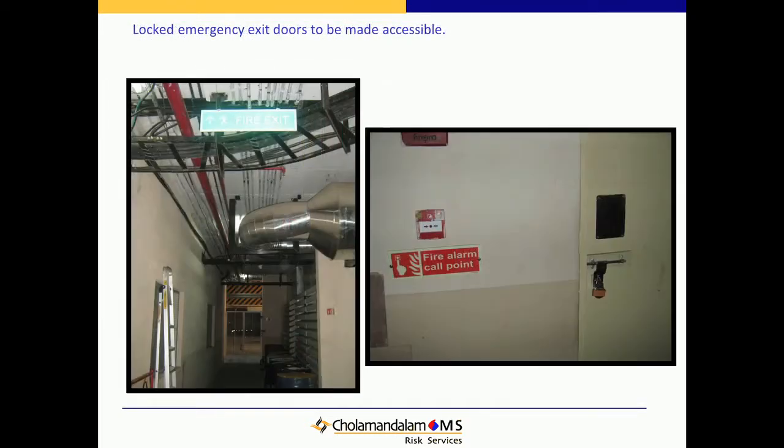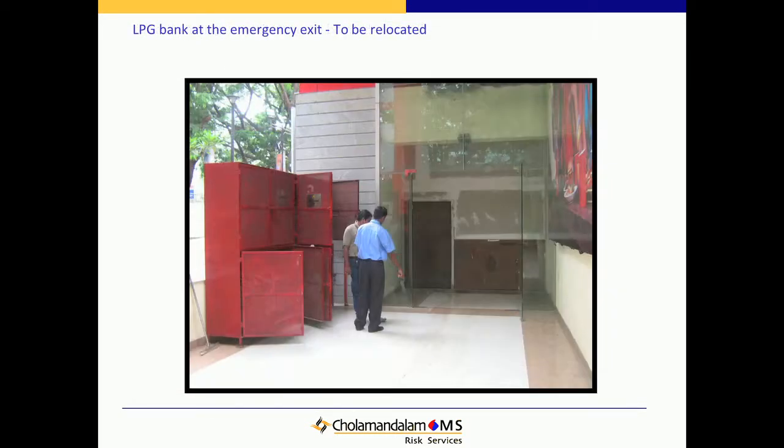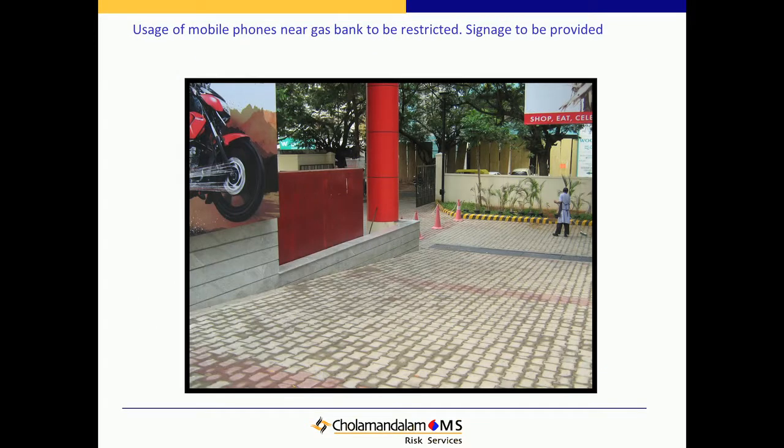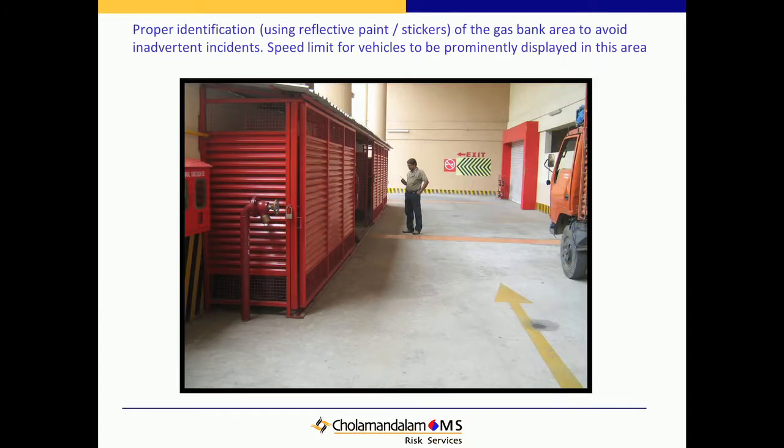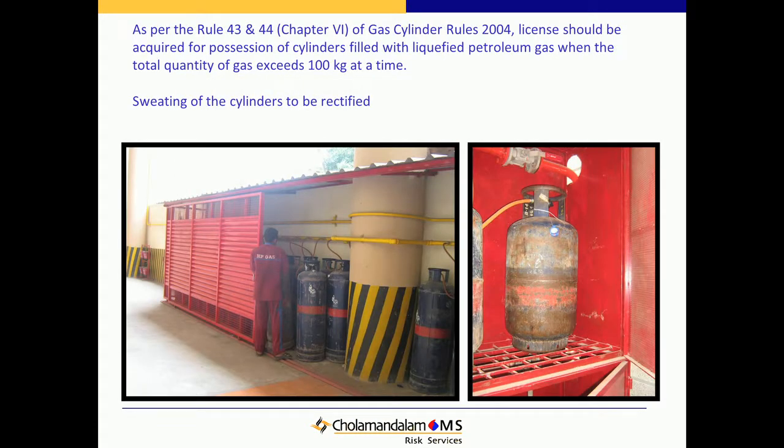See, you have a lot of LPG cylinders that are used for the kitchens there. See how they are located in the area where the vehicles are moving. So there is a possibility of them getting damaged by vehicles hitting them, and they are not properly secured. There are no gas detection systems there. It's quite risky.